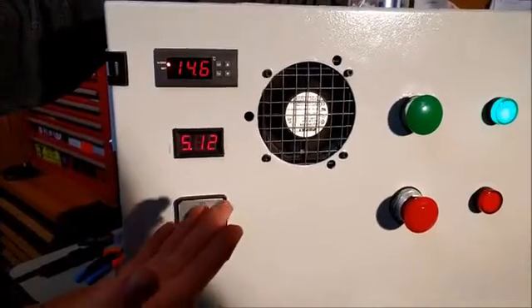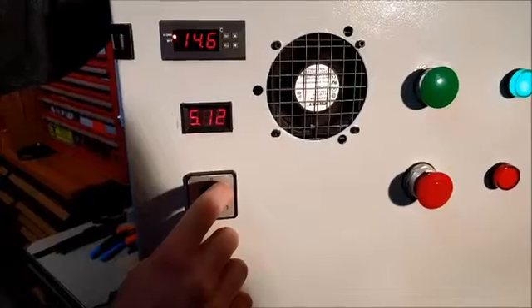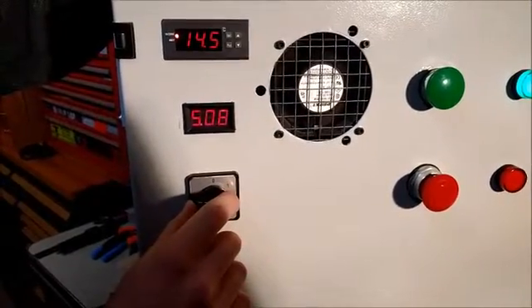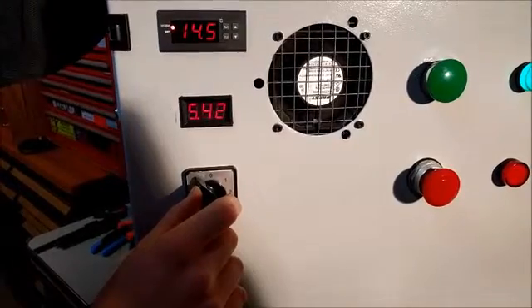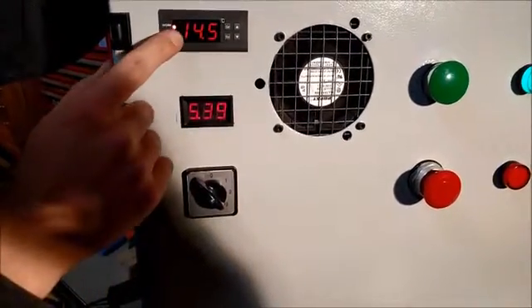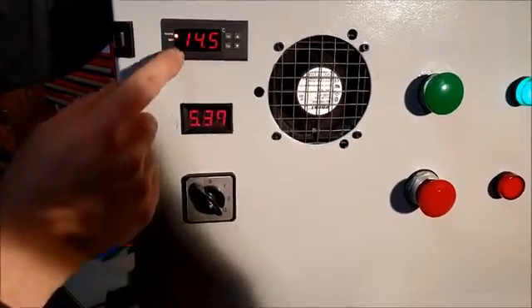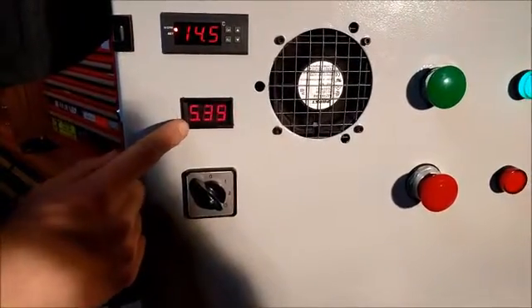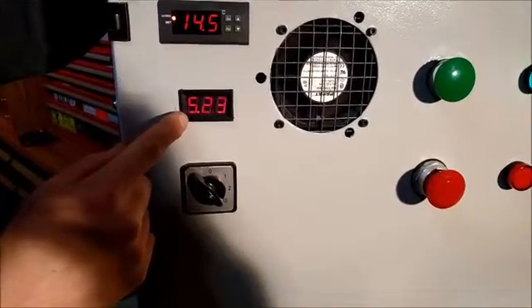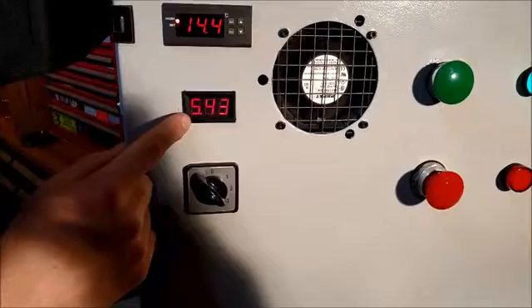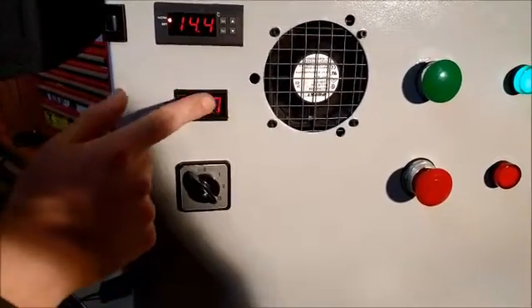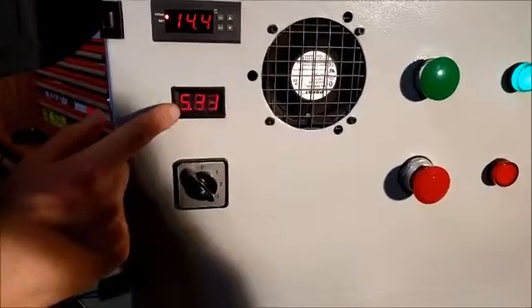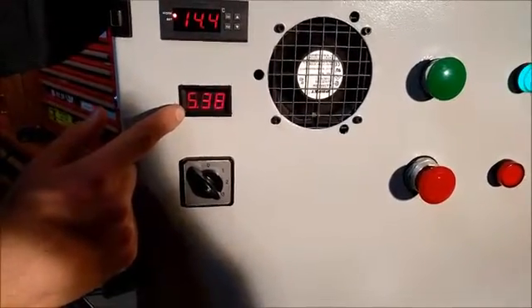I have the fans on three separate speeds, so you can probably hear them pick up. Right now we're at 14.5 degrees, we're gonna run it on high, we'll see if that drops. Right here, this is the voltage coming from one of our power supply units. It's actually a health voltage, so 5.25 volts is the healthy voltage. If it reads anything other than that, I know there's a problem with my main power supplies.